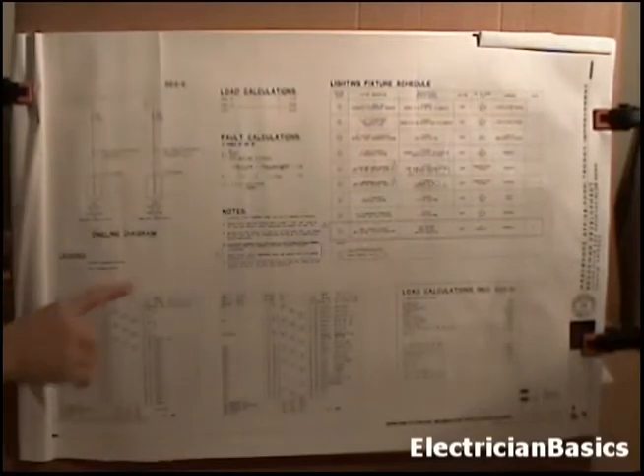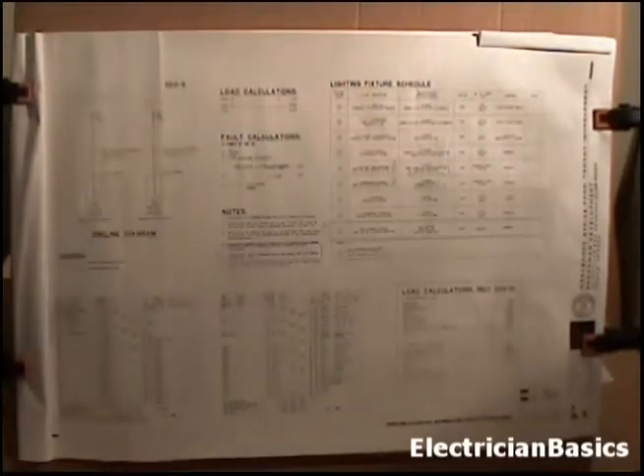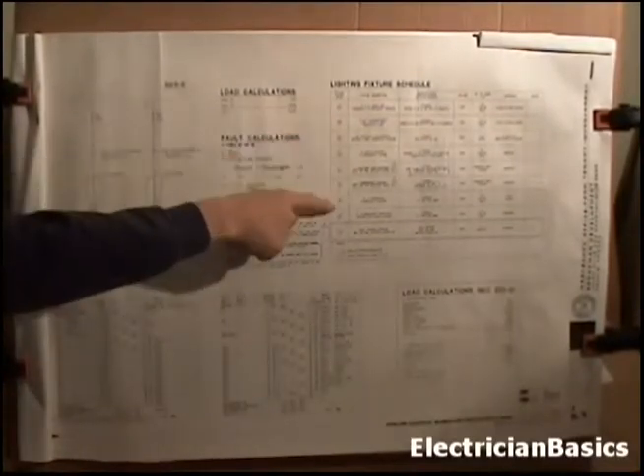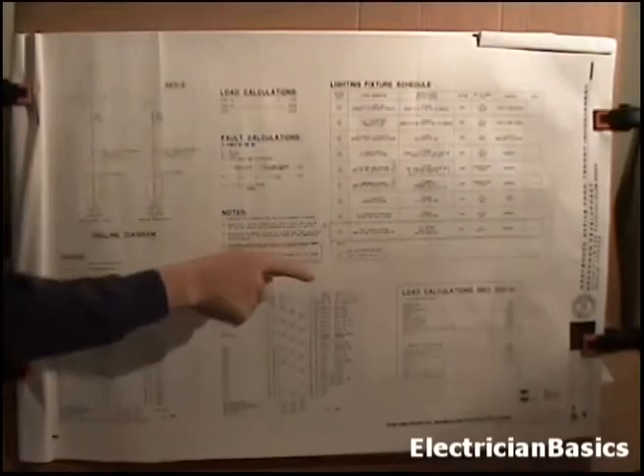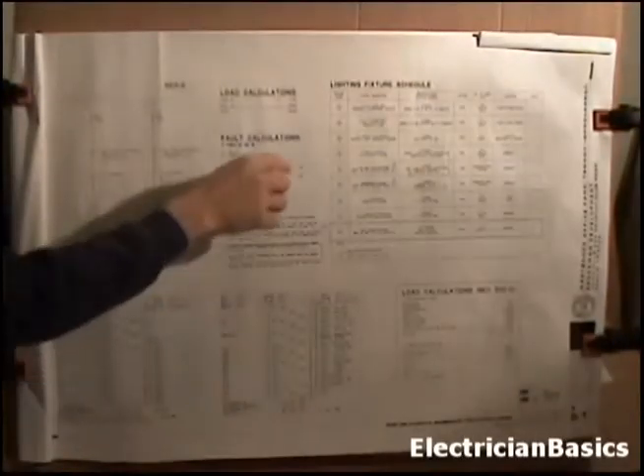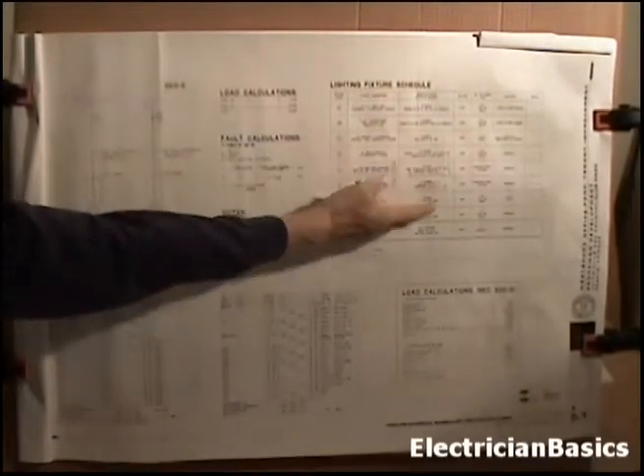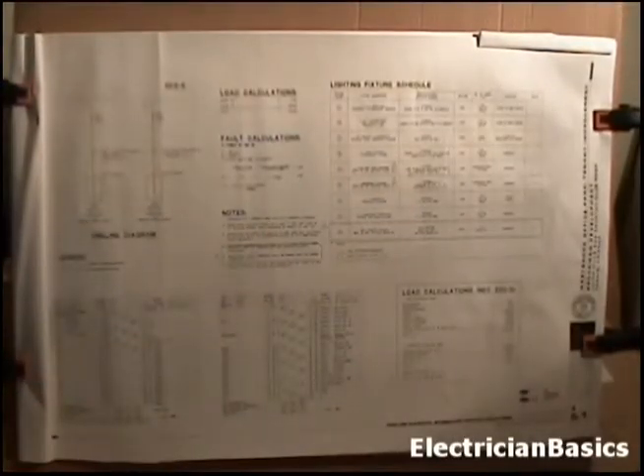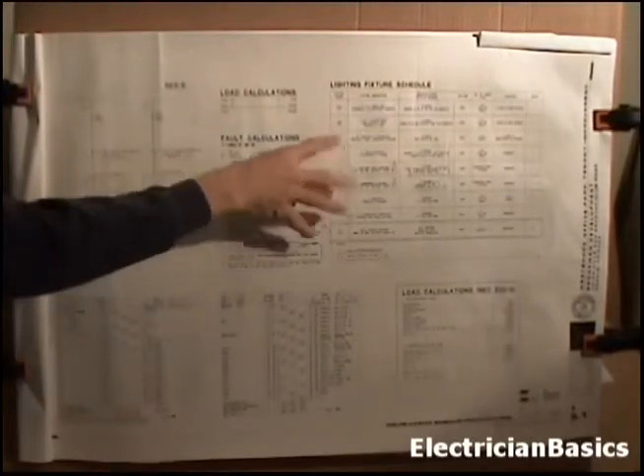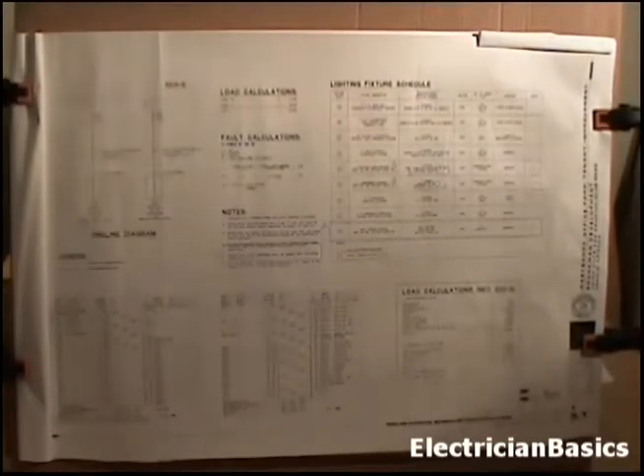Let's look up in the top right hand corner. We have the lighting fixture schedule. We already took a close look at that when we were doing the lighting plan from sheet E 3.1, and you remember we have these hexagons with numbers. These are hexagons with letters. So those are the fixture types, and we get a description, manufacturer catalog number, the voltage, the number of lamps required, and the type of mounting. And this is pretty straightforward. We covered that when we looked at the details of some of the light fixtures on the lighting plan. We've already looked at that, but again, just go over it again as a review and make sure you understand thoroughly how the lighting fixture schedule works.